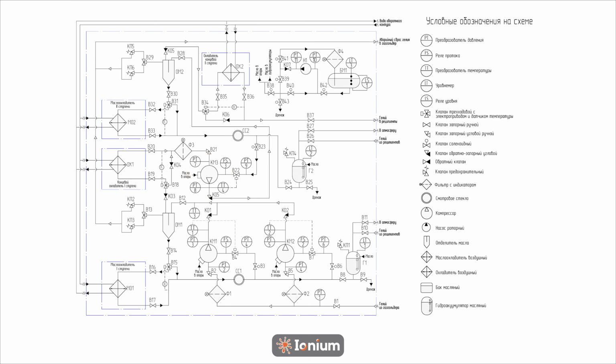Along the screw axis, oil from the water-oil heat exchanger, cooled to about 28 degrees Celsius, is injected from device MO2, flowing at about 31 cubic meters per hour, under compression pressure, with negligible hydraulic losses within the oil separator and cooler, at approximately 21.6 bar absolute.